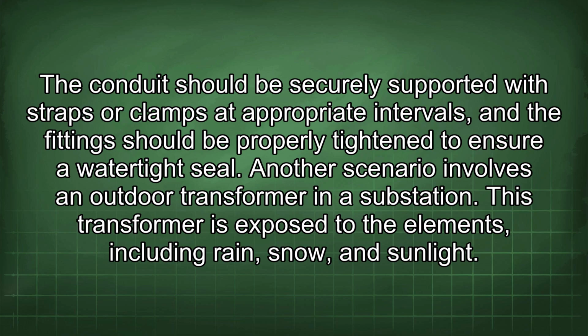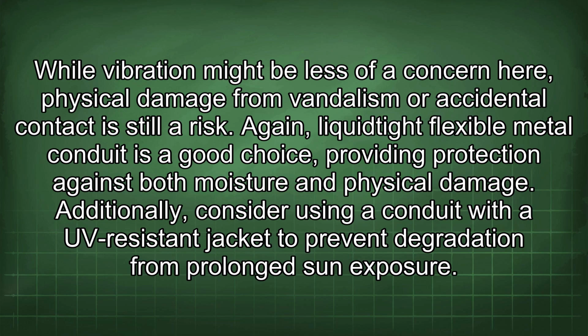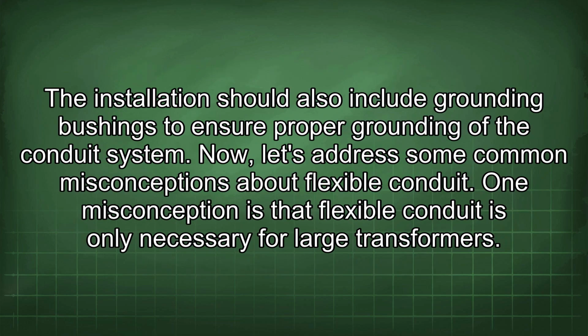Another scenario involves an outdoor transformer in a substation. This transformer is exposed to the elements, including rain, snow, and sunlight. While vibration might be less of a concern here, physical damage from vandalism or accidental contact is still a risk. Again, liquid-tight flexible metal conduit is a good choice, providing protection against both moisture and physical damage. Additionally, consider using a conduit with a UV-resistant jacket to prevent degradation from prolonged sun exposure. The installation should also include grounding bushings to ensure proper grounding of the conduit system.